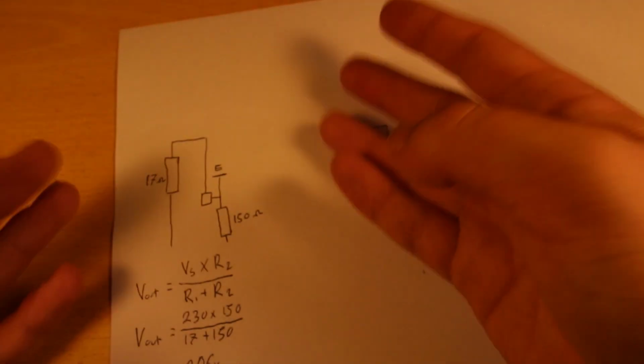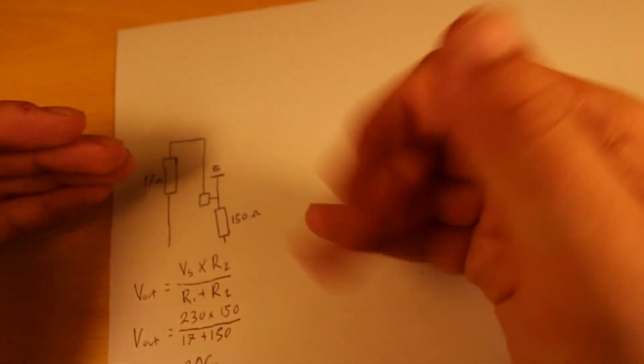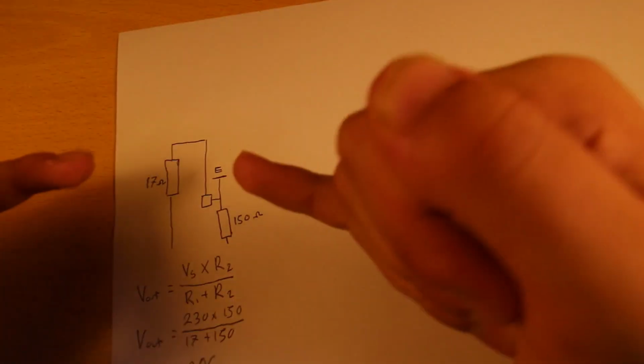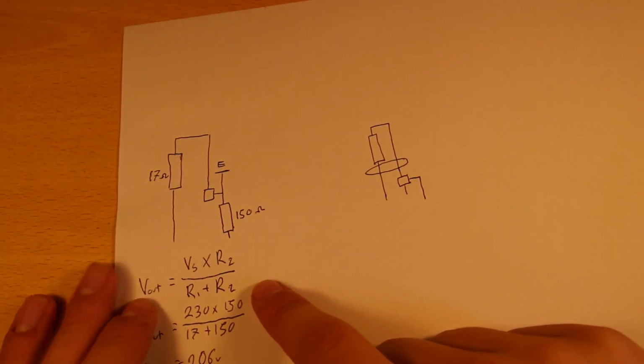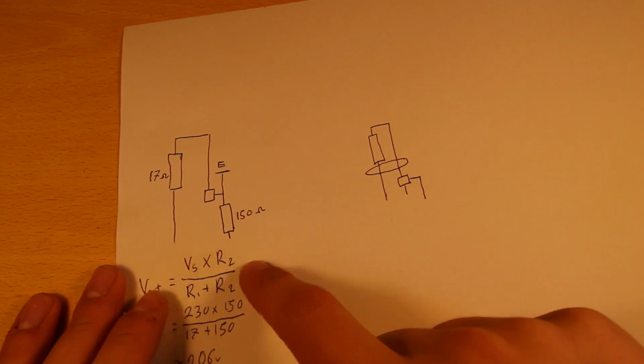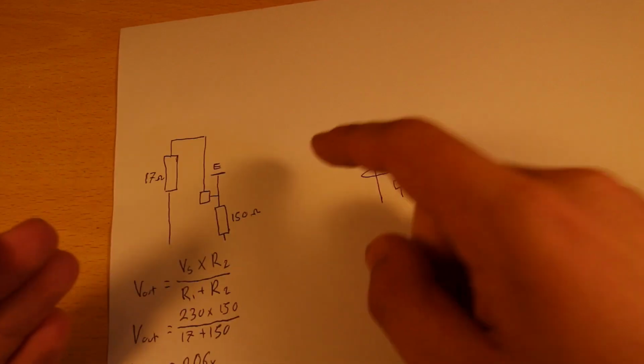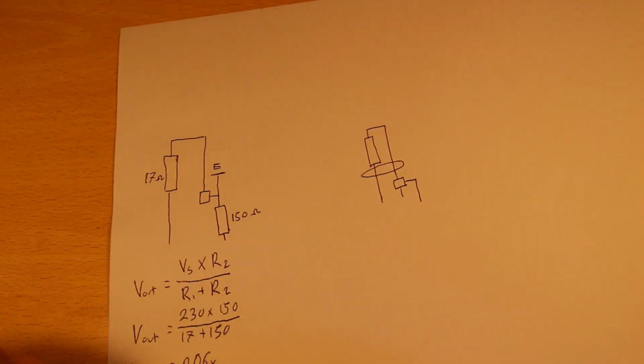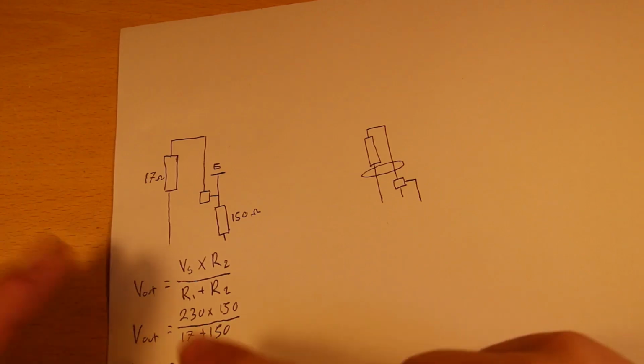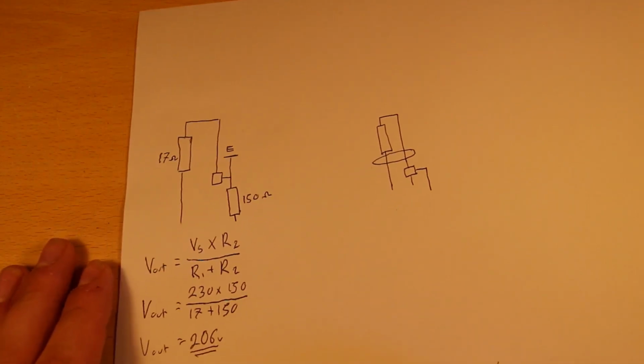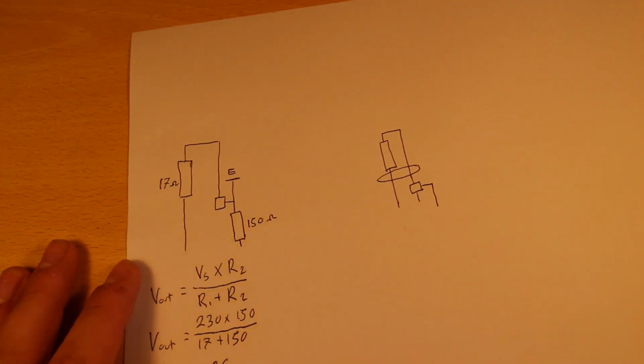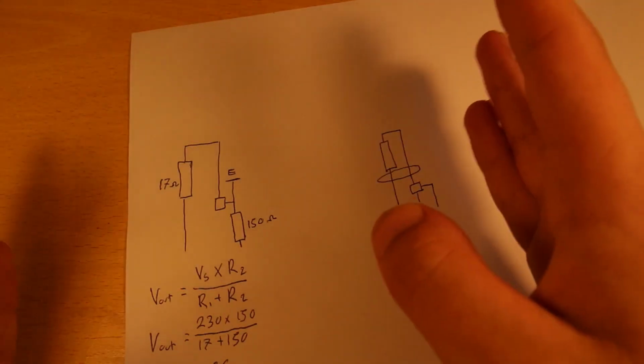Your earth rod, let's say, has 150 ohm impedance, so we are putting a 17 ohm resistor in series with a 150 ohm resistor. We now have a voltage divider. So using this formula, the output voltage is equal to the input voltage times R2, which is this one here, divided by R1 plus R2. That gives us 230 times 150 divided by 17 plus 150, which gives us an output voltage of 206 volts. So that means that this point here will be 206 volts above the actual earth. 206 volts is still more than enough to kill you if you touch it, so an earth rod will not fix the problem.